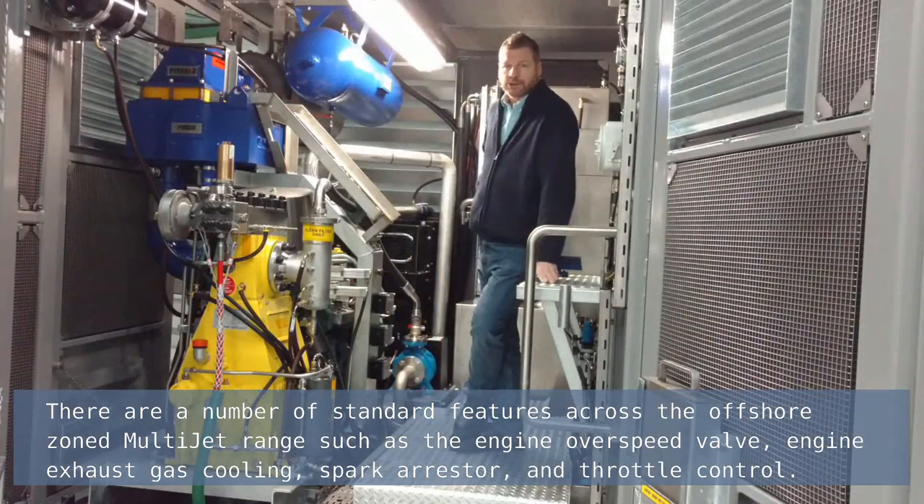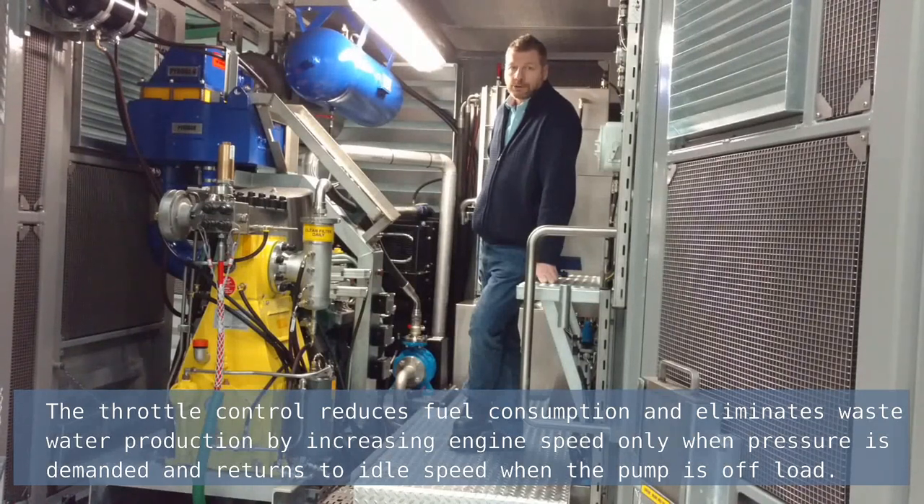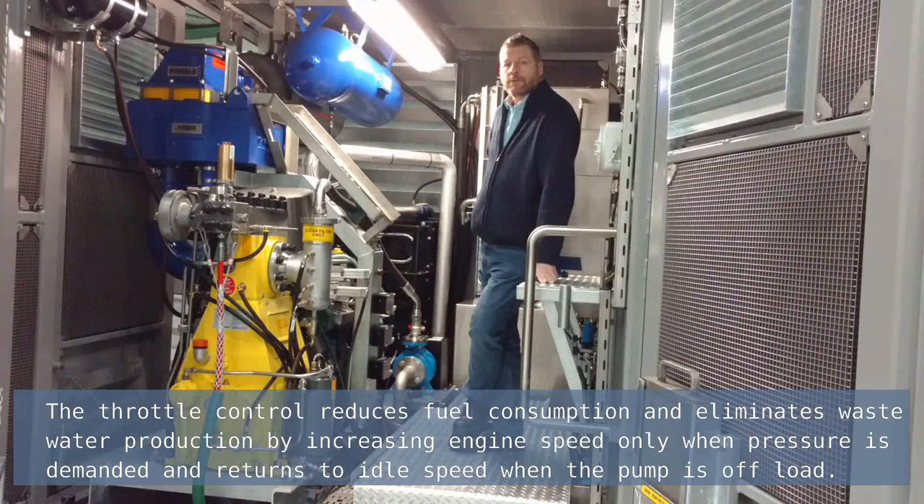There are a number of standard features across the offshore zoned MultiJet range, such as the engine overspeed valve, engine exhaust gas cooling, spark arrestor and throttle control. The throttle control reduces fuel consumption and eliminates waste water production by increasing engine speed only when pressure is demanded, and returns to idle speed when the pump is off load.